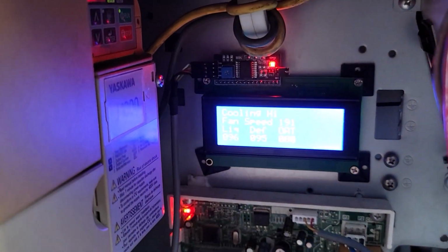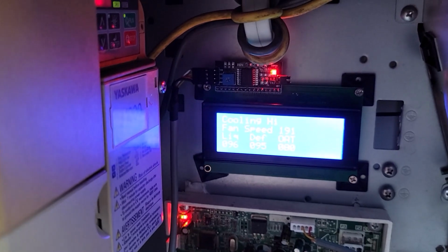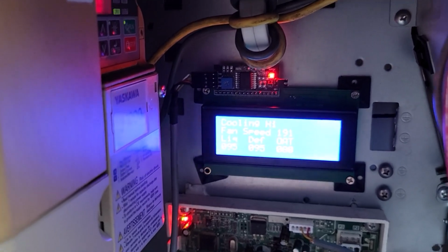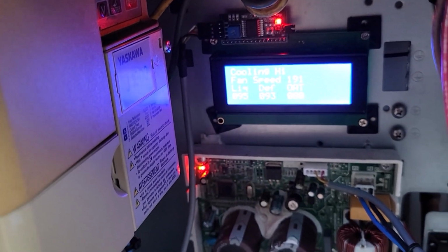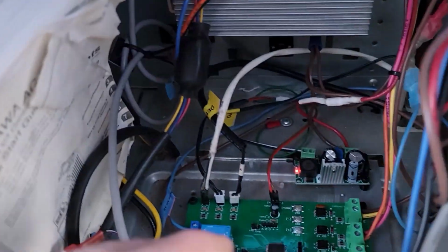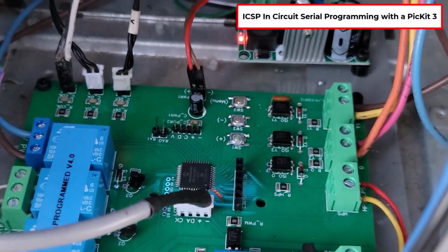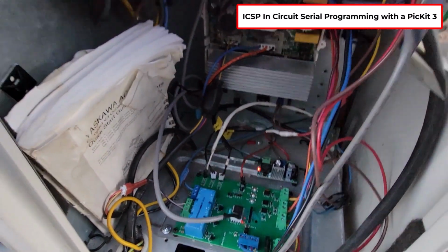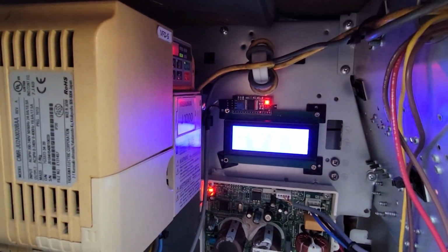And if it drops too much in the liquid line temperature, I might have to program that a little higher than I thought. And I didn't put it in where I could program it out here. I could actually go and program it in the code and then update it, which I could do, and just take my programmer out here and plug it in right here. Just drop in the new program, change it to version 5.0 or something, right? So it started to drop, 92, 93.